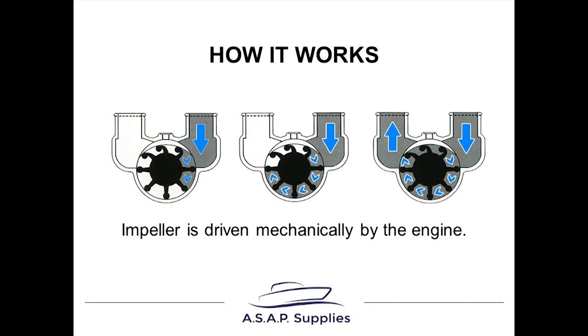Here's how it works, driven by the engine. You can see the impeller spinning - it would be spinning clockwise. The inlet pump fills up. This top piece here is a cam, and that compresses the impeller. You can get different thicknesses - half cams, quarter cams, full cams. The thicker the cam, the shorter the impeller life you'd get, but the more water it'll pump. Engine manufacturers do tests with the engine to determine which one's best to suit their engine.